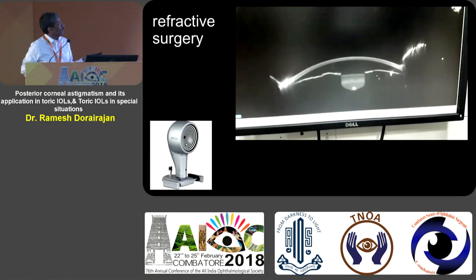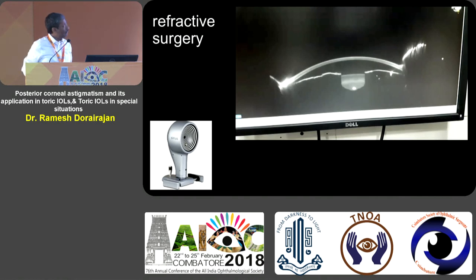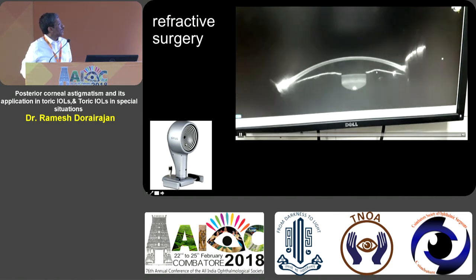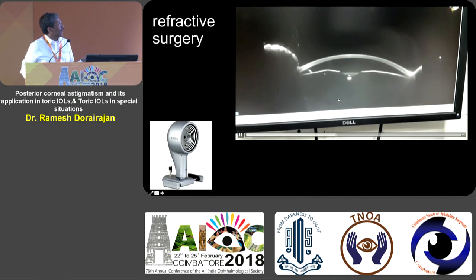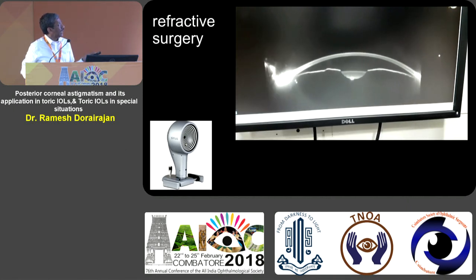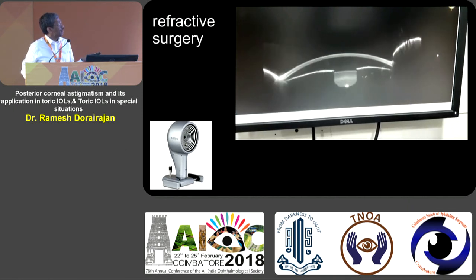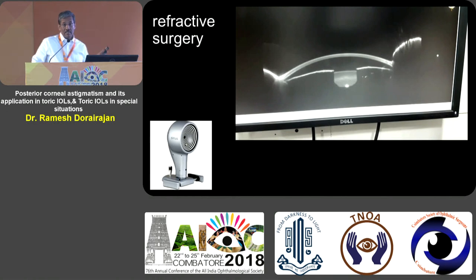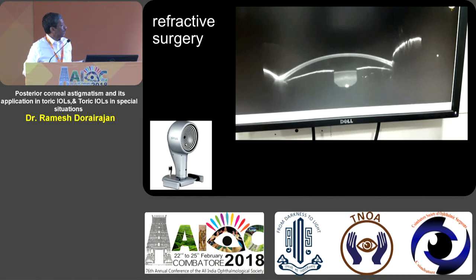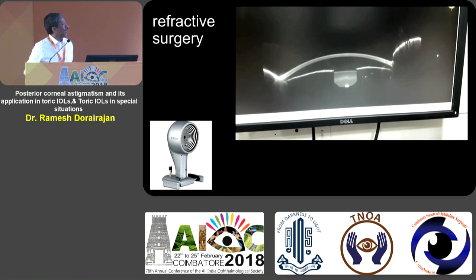If you want to find out where the Gullstrand ratio is altered, you need a machine that also measures the posterior cornea — one that gives a slit image where both the front and back are measured. If your printout shows only rings, you are measuring only the front. Only when you have a machine that measures both and gives a slit image will you have the full posterior corneal data.